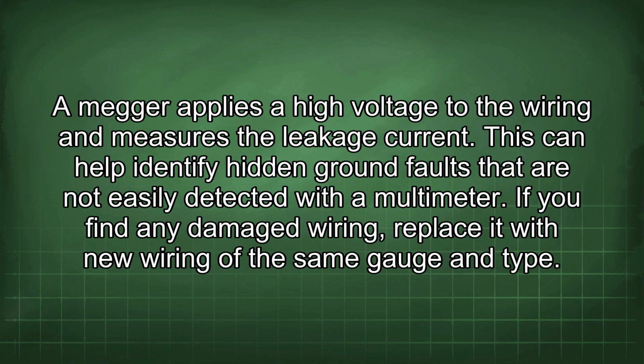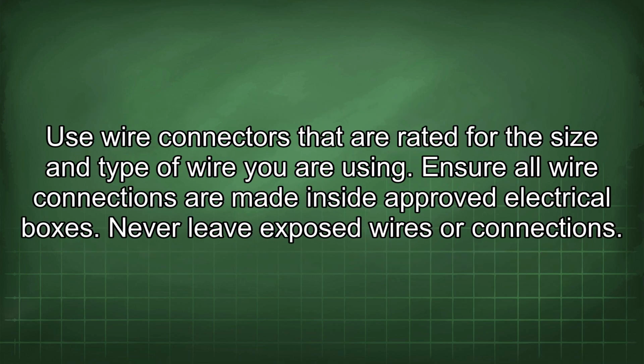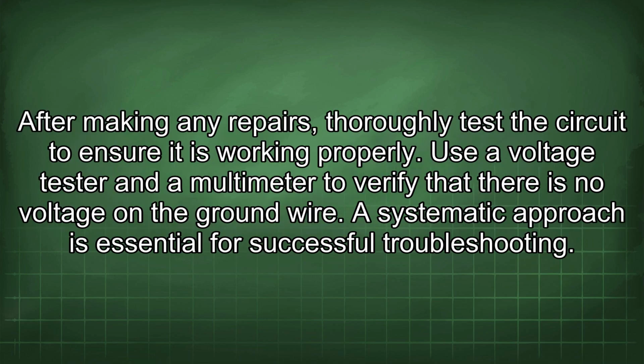If you find any damaged wiring, replace it with new wiring of the same gauge and type. Use wire connectors that are rated for the size and type of wire you are using. Ensure all wire connections are made inside approved electrical boxes. Never leave exposed wires or connections. After making any repairs, thoroughly test the circuit to ensure it is working properly. Use a voltage tester and a multimeter to verify that there is no voltage on the ground wire.